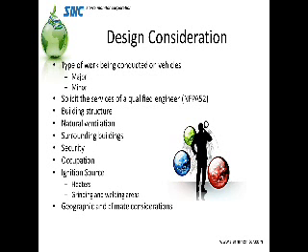In the occupied areas of your building, it can sometimes be beneficial to pressurize those particular areas so that you don't have to have gas detection in, so none of the natural gases or other fuels can migrate into those areas. Also identify where the ignition sources could be: heaters, grinders, welding areas. Can these be consolidated into one area and then cordoned off? These are the types of things. If there's a heater in there, you want to keep in mind that the heater can't have an open flame, the result of which could cause an explosion, so you may have to change your heater out.